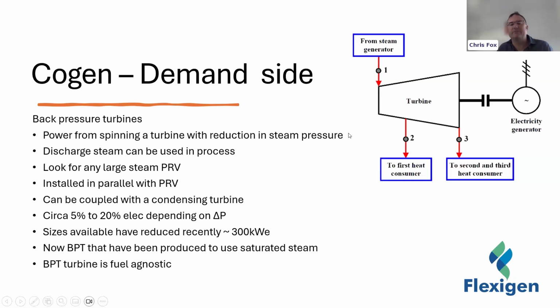In the case of a back pressure turbine, the goal is different - it's to take the discharge pressure down to whatever your plant needs. So rather than chasing every bit of electricity, if your plant needs 10 megawatts of thermal heating at 8 bar, the idea is you come in at a higher pressure than needed, and the back pressure turbine takes it down to 8 bar, then you feed your process with that.